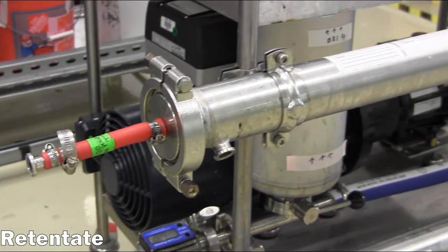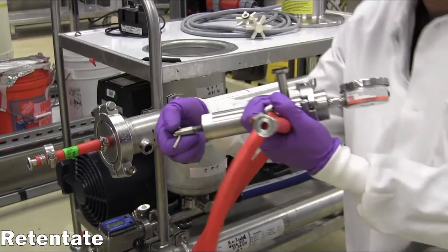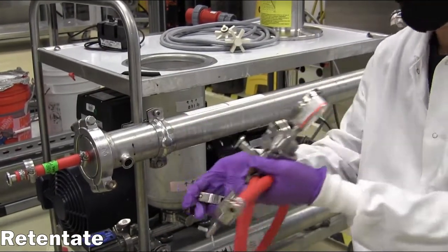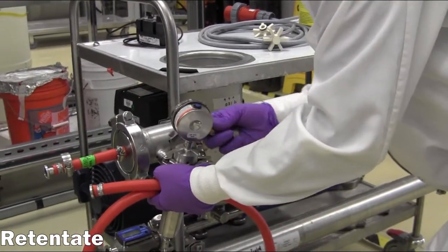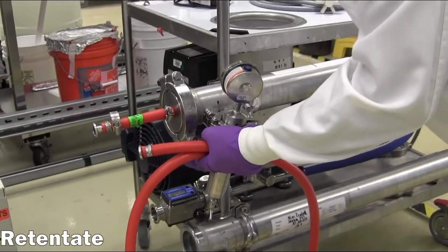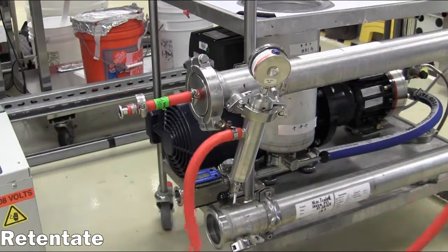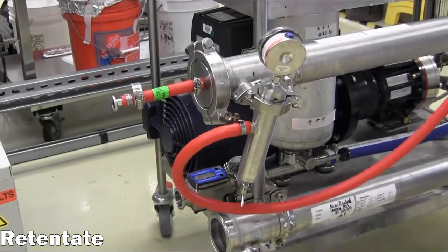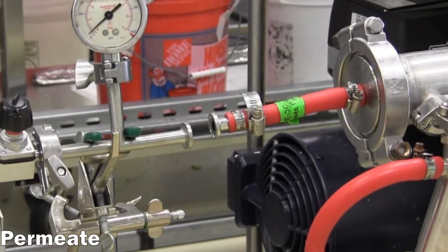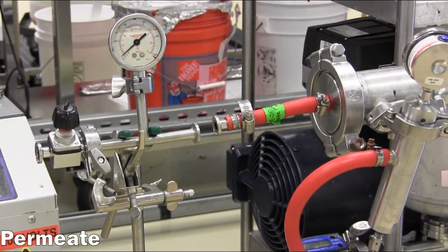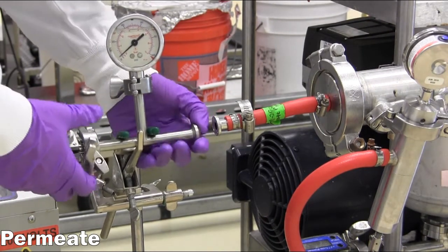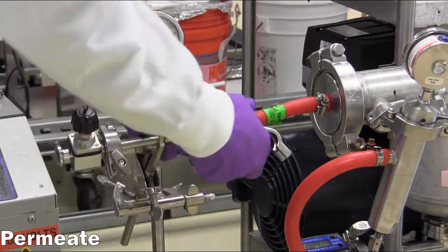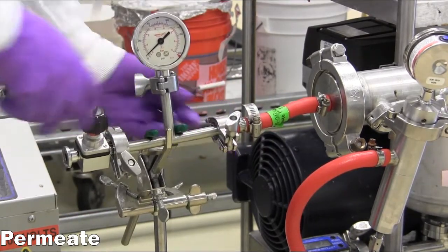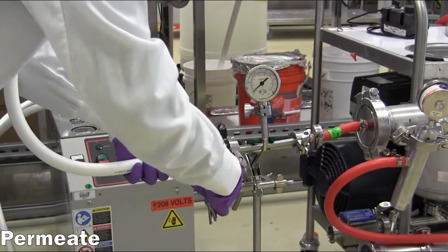At the outlet end of the filter housing, a retentate manifold is connected to the outlet on the outside of the filter housing. The manifold includes a back pressure valve, a pressure gauge, and a hose to route the retentate flow to an external vessel. Likewise, the permeate manifold is connected to the outlet port in the center of the end cap, which includes a pressure gauge, hand valve, and a hose to an external vessel.